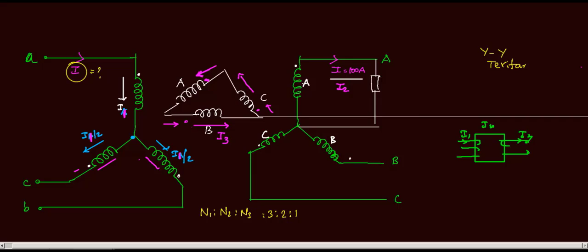So what is the purpose of the tertiary winding? It is to balance the currents, since phase B and phase C get a current due to the secondary current from the unbalanced load. Phase B and phase C MMF balance is not achieved, so I am placing the tertiary winding to get the MMF balance. Let's see the MMF balance of phase A.